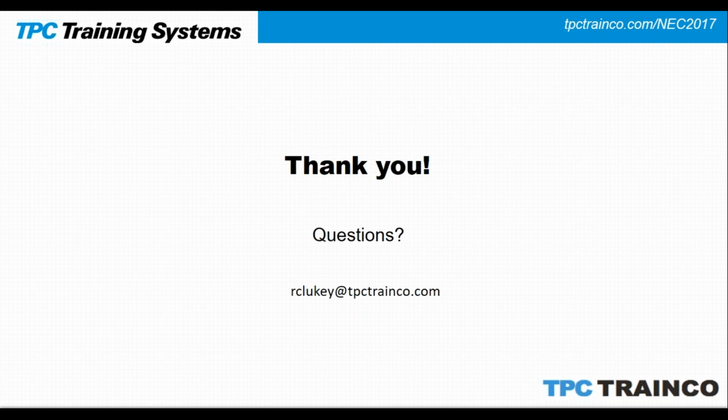So even though we have to install the fault current and the clearing time and the voltage at the time of installation, that is great. As soon as that equipment has been accepted by the building owner and we're now utilizing that equipment, we have to have another label on there that complies with 70E. All right. Thank you, Bob.